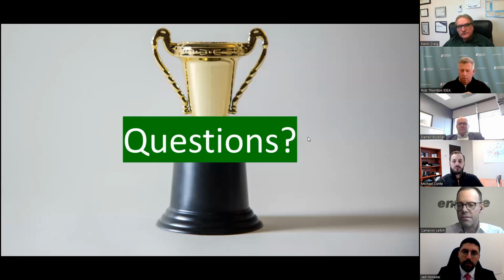Thanks, Rob, I think that's exactly right. If you're talking purely on dollar per unit energy purchased from the utility, running a natural gas boiler would be 4 or 5 times less expensive than an equivalently sized electric boiler. In Ontario, electrical utilities charge based on demand and consumption, so if you turn the electric boiler on the last day of the month, you'll see much higher relative pricing. But with reasonable assumptions around utilization, demand, and consumption, it's in that range. You need the COP of the plant to overcome that shortfall on the cost of electricity.